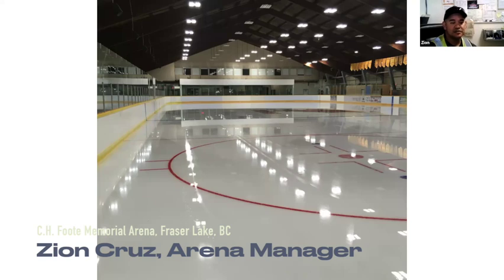We saw a substantial decrease in compressor runtime pretty much right away in the first season when we dropped our flooding temperature from 165 degrees all the way down to about 60 degrees. So losing that 100 degrees of heat really helped in how our compressors run. We find the runtime was almost cut in thirds. Well, that's a substantial difference.